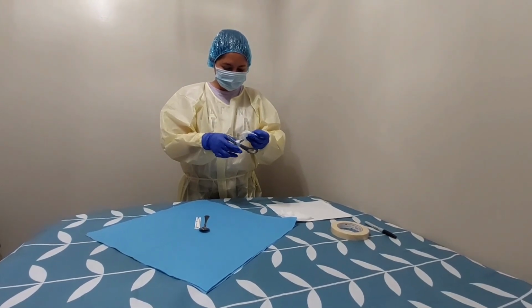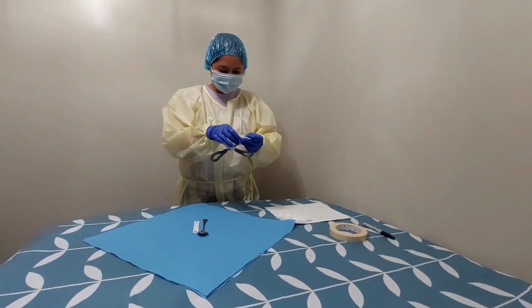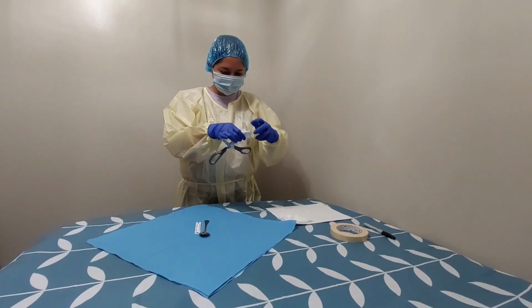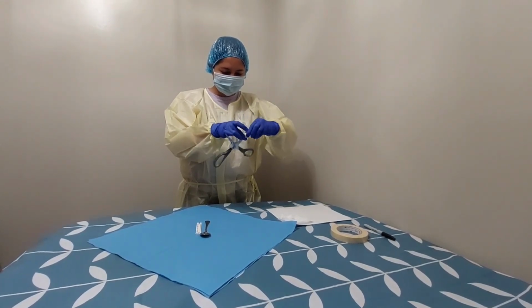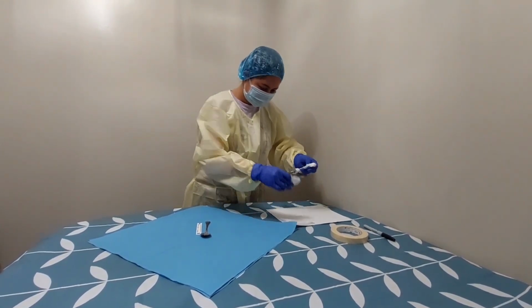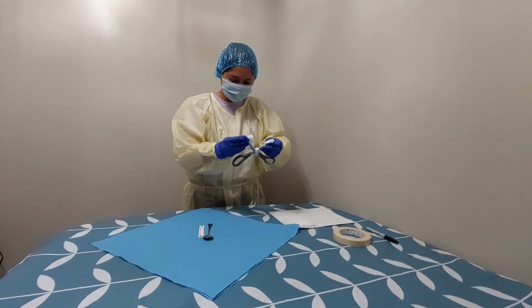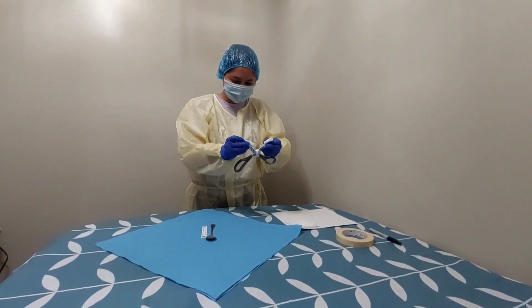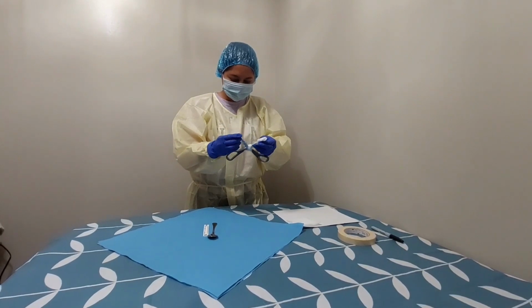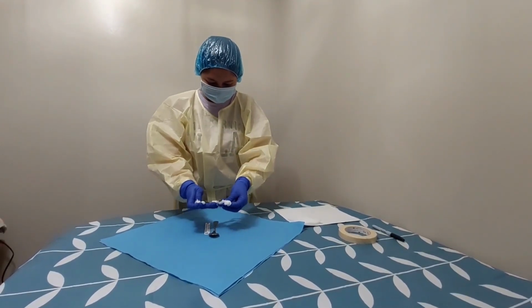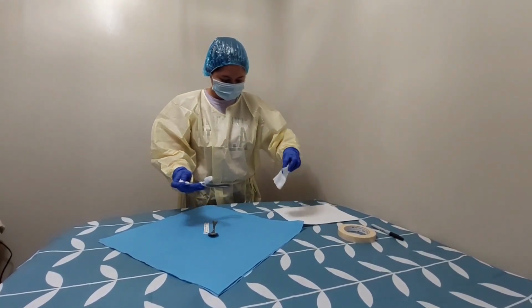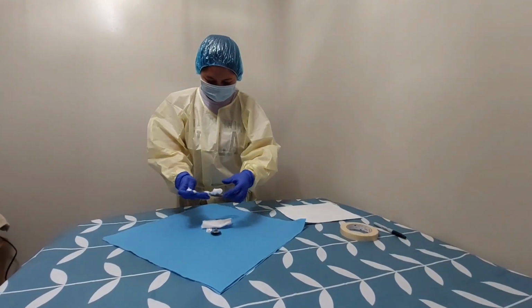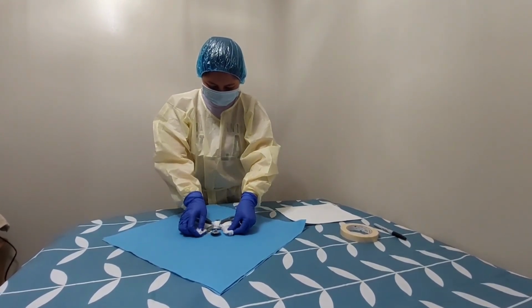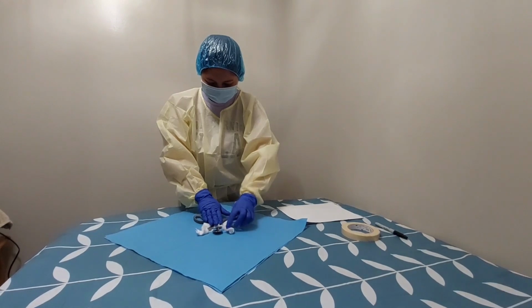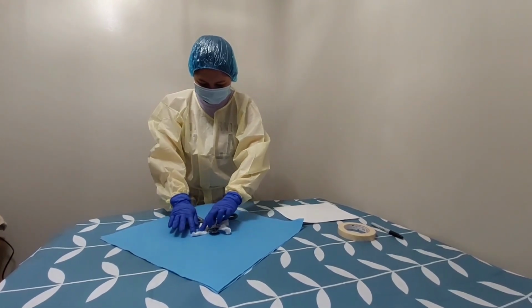Place gauze between any hinged instruments and keep all ratchets open during the sterilization process. All sharp tips on instruments must be protected with tip protectors or gauze. Keeping the instruments open ensures that all parts of the instruments are sterilized, and covering the sharp tips prevents the packages from being punctured.